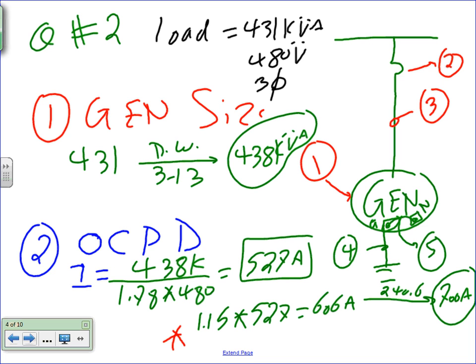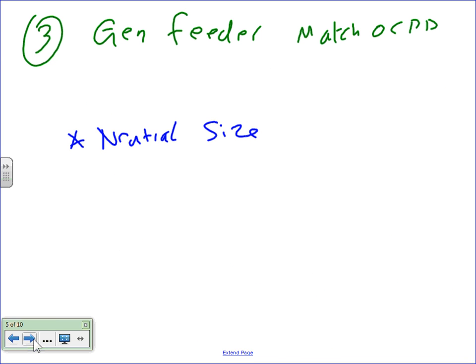The 1.15 is coming from 445 dot something. 445 dot what? Dot 13. Okay, and this is usually for conductors. If you go there, it's for conductors. I size the overcurrent device to protect the conductors. Okay, so let's write it down. Where did that come from? This is 445.13. I can't emphasize enough, this is for conductors, but I use it to size the overcurrent device because I match the conductor to it. Okay, next, generator size.